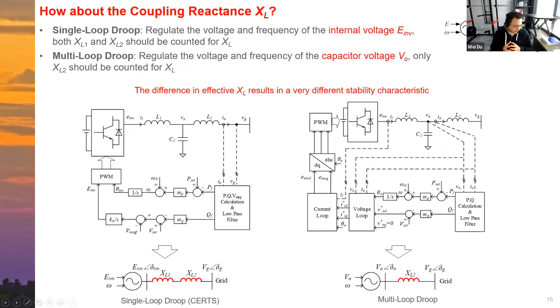If we review the basic concept of the grid-forming inverter, we know that it behaves as a voltage source behind an impedance. So for those two controls, where is the equivalent voltage source and where is the equivalent coupling reactance? We need to find out by analyzing those two controls. For the single loop droop control, as I mentioned, the PF droop control regulates the phase angle of the modulation waveform and the QV droop control regulates the magnitude of the modulation waveform. So this control actually treats the internal modulation waveform, or the bridge side voltage, as a controllable voltage source. The controller just regulates the magnitude E and the phase angle of this internal voltage, also the modulation waveform. Then at the fundamental frequency, it behaves as a controllable voltage source behind impedance L1 and L2. So both XL1 and XL2 should be considered as coupling reactance, because it's regulating the phase angle and the magnitude here.